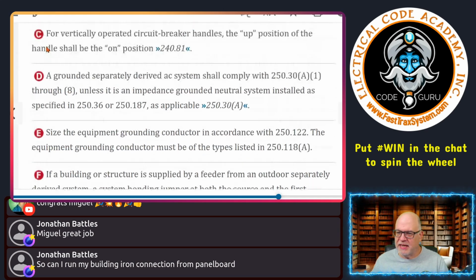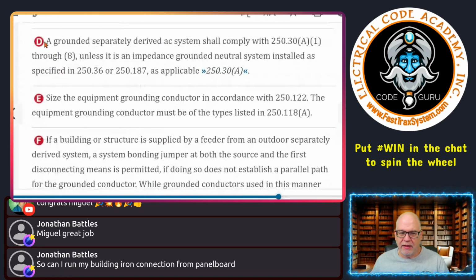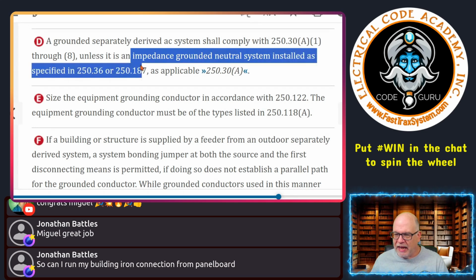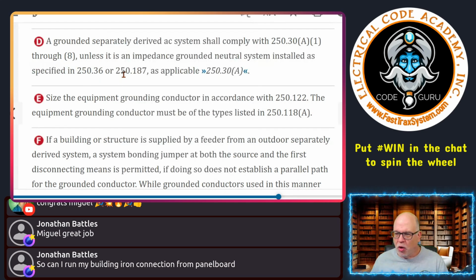Next, it says D. It says a grounded separately derived AC system shall comply with 250.30A1 through A8 unless it is an impedance grounded neutral system installed as specified in 250.36 or 250.187 as applicable in 250.30A. Okay, so separately derived systems, okay, we have to follow all the rules just like it was a normal system. We're going to have to establish a grounding electrode system.